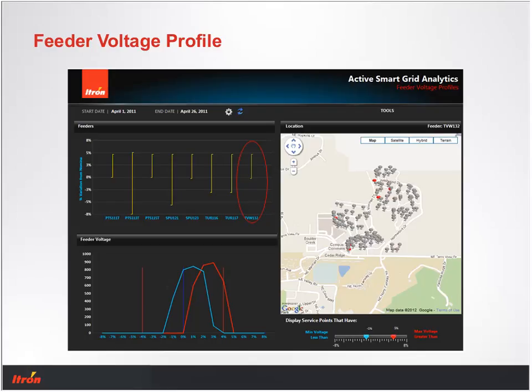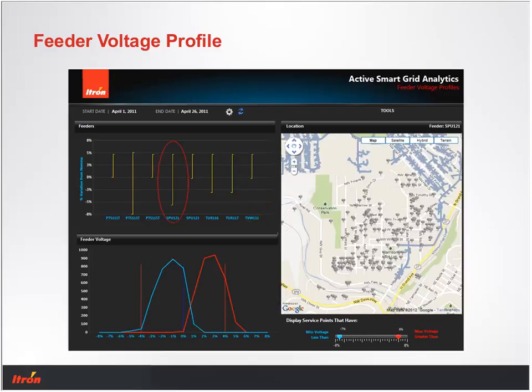When we look at those feeder bars in the upper left, the ones that are shorter immediately show some opportunity for voltage reduction, because of where they're placed and the narrow nature of that band. As we get into feeders with a longer appearance, you can see by the length of that line that the high and low voltage distribution is more spread out, and you can also see how far apart they are in the curves in the lower left. We like the curves to be fairly narrow, but when the high and low are separated far enough, that feeder might have some difficulty being reduced.